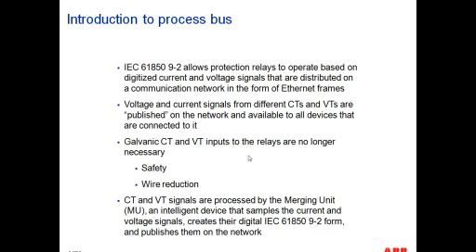And galvanic CT and VT inputs are no longer necessary from that perspective. And what this results in is that you now have an isolation at the back of the relay from the primary equipment, which results in a safer installation and also, of course, results in wire reduction. At the same time, the IEDs are leaner because they will not require transformer boards or other components that are currently needed when processing current and voltage signals from conventional instrument transformers.